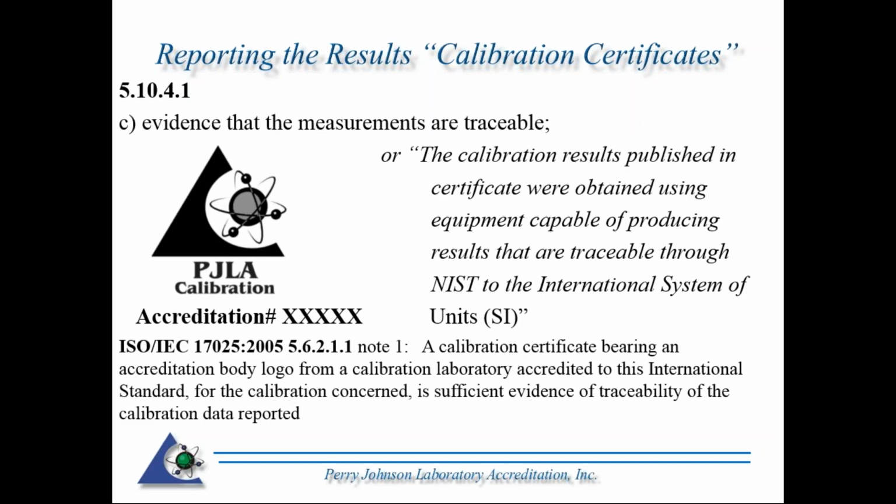All right, switching gears from uncertainty, still on calibration certificates. Evidence that the measurements are traceable. That could be provided in one or two ways, or in both ways within the certificate. One evidence of traceability is the actual logo of the accrediting body, provided they are part of the ILAC MRA, Mutual Recognition Agreement, which, of course, PJLA we are.